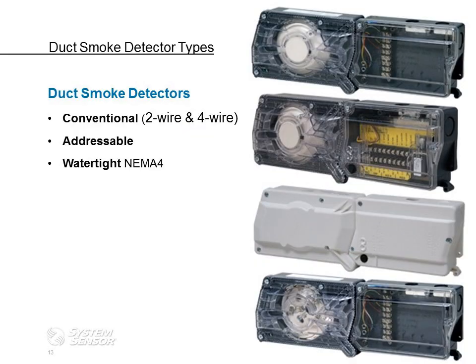Now, the types of duct detectors that are available in the market: conventional duct detectors, both two-wire and four-wire, and intelligent addressable duct detectors, also available through fire panel manufacturers, OEM partners. And then we also have a watertight housing, which is a NEMA 4 rated. The advantage, obviously, of the watertight housing is that it eliminates the cost of a third-party enclosure when you're trying to maintain a watertight NEMA 4 listing.